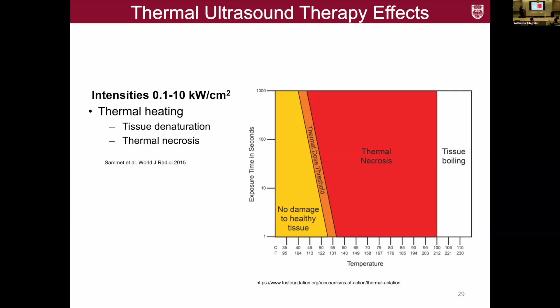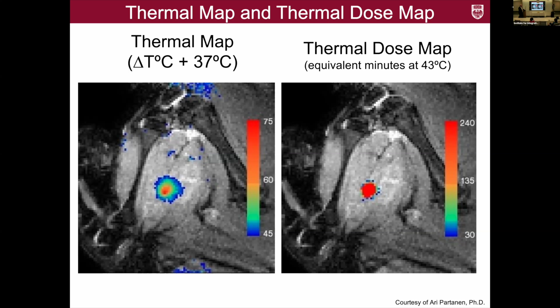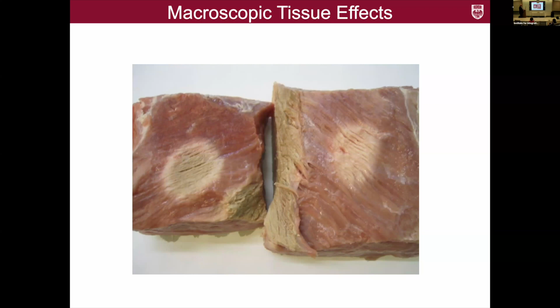And this is the thermal dose threshold here. So we have to be careful that we don't damage the surrounding tissue. This is a typical thermal map and a thermal dose map. On the left side is the thermal map, on the right side is the thermal dose map. And this is what we achieved now in muscle tissue. You can nicely see the coagulative effect here, and then in the rim there is already some damage, but you can really nicely focus the ultrasound beam to achieve this macroscopic effect.